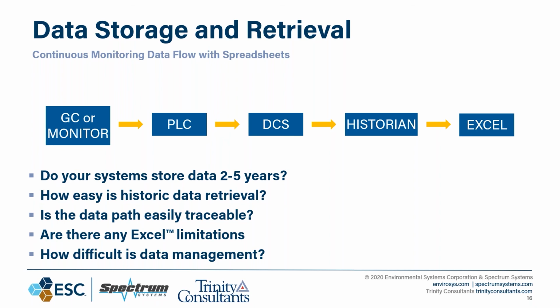Another helpful tip is to go to your analyzers themselves. Typically there's a buffer setting for data - it could be 2 weeks, 30 days, or a year. Sometimes I've come into these facilities and recognized that something was reset, or the analyzer was restarted, or they simply updated some firmware and that setting was not on. So if they had a crash elsewhere, you've lost data.